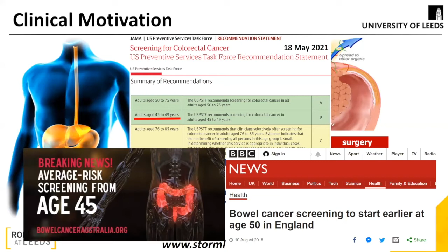The best way to screen for colorectal cancer is by colonoscopy, using a flexible endoscope. This is a 1.5 meter long tube with a camera and illumination at the tip, and an irrigation channel to clean the camera or to insufflate the collapsed lumen, allowing for visualization. The tip can be articulated in 2 directions by cable steering, with the cables at the tip connected directly to 2 knobs controlled by the thumb of the operator. The flexible endoscope also has a channel to allow access for endoscopic instruments to interact with the tissue and collect biopsies for further lab examination, or remove polyps, which are precursors of colorectal cancer.